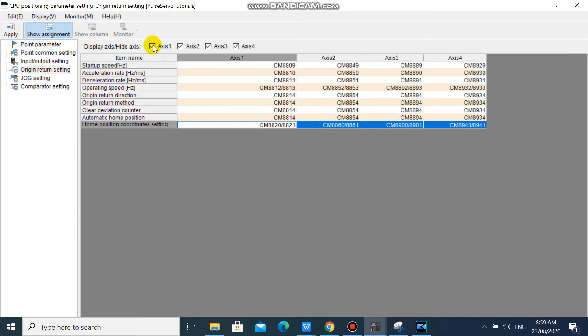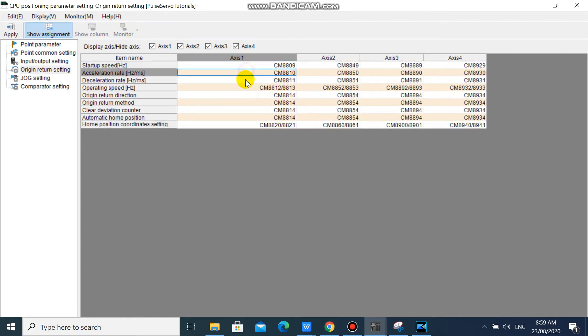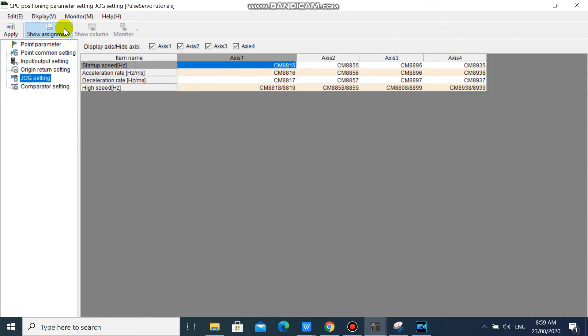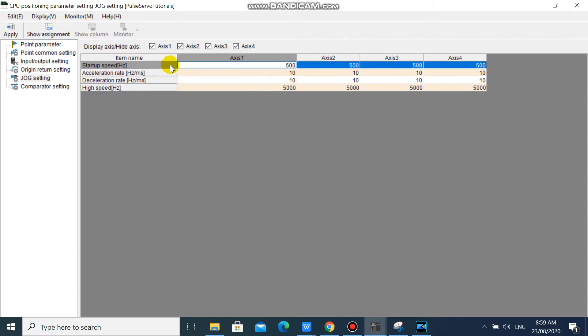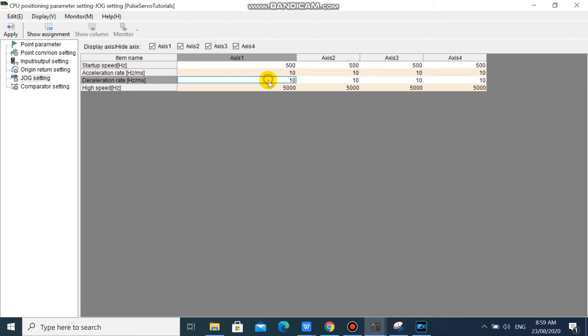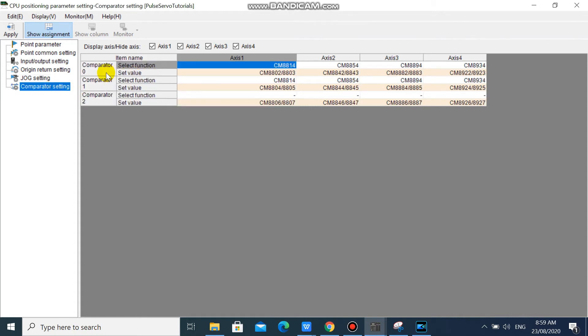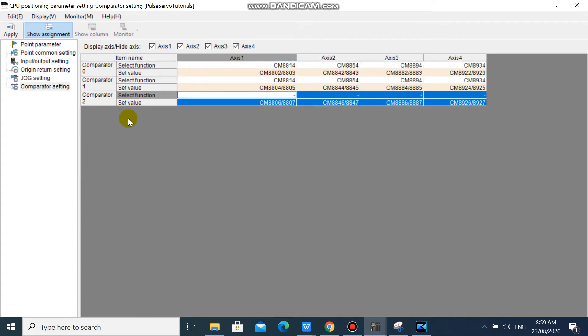You can also see the device assignments. You can change these device values in ladder if you want. In your jog setting, the default startup speed is 500. Your jog acceleration is 10, deceleration is 10, and your jog high speed is 5000. You can also change these values in your ladder using a move instruction. We will leave comparator setting to its default settings. Then click Apply.